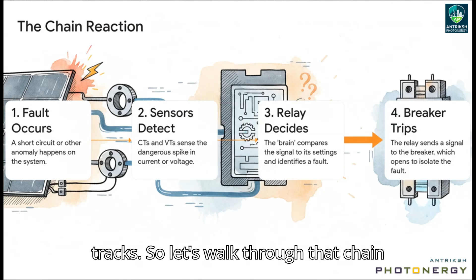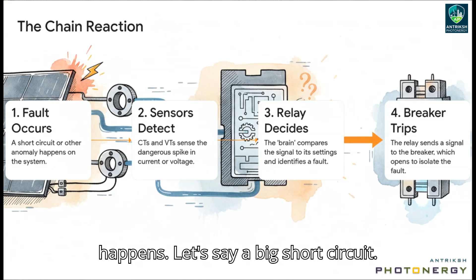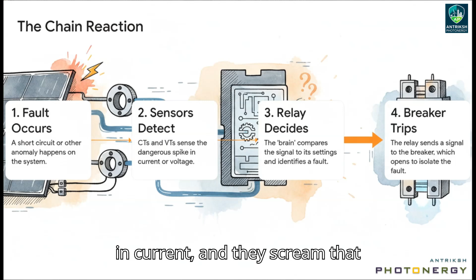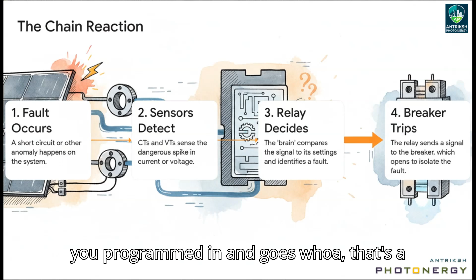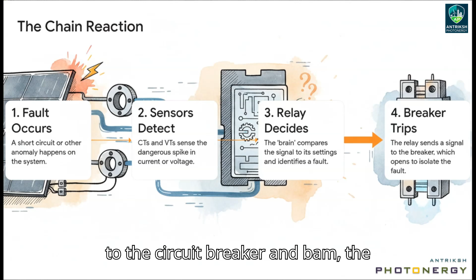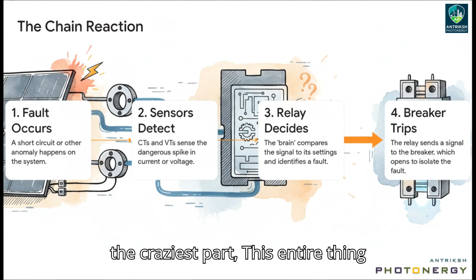Let's walk through that chain reaction step by step. A fault happens, say a big short circuit. Instantly, the CTs sense this insane spike in current and scream that information to the relay. The relay takes one look, compares it to the settings you programmed in, and goes, whoa, that's a fault. It immediately fires a trip signal to the circuit breaker, and the breaker opens, isolating the problem. The craziest part? This entire thing happens faster than you can blink. Now let's zoom in on that core component.